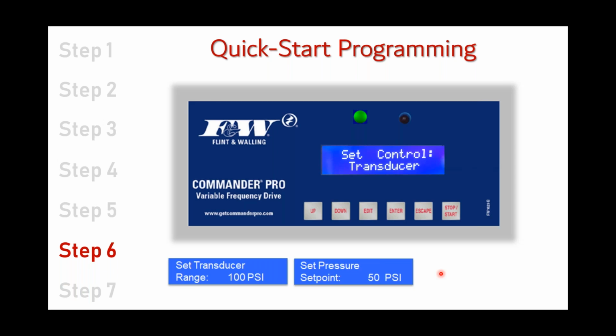You take a hex-headed screwdriver, you put it down into that black tower, and you turn this hex-headed nut clockwise if you want to increase the pressure, counterclockwise if you want to decrease the pressure. It's very much like a conventional pressure switch. You're probably going to have to look at a gauge as you're turning this.